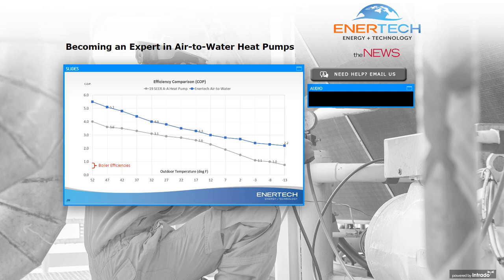If it's a product that's designed specifically for low temperatures and is specifically designed for heating, as you can see from that blue line, even at minus 13 Fahrenheit, we still have a COP of 2.2. And I've always looked at heat pumps, from a design standpoint, as: where do we want to turn it off? If our COP is around 1, it doesn't really make a lot of sense to run that heat pump. But if we can stay in the 2 range or so, then we're better off making heat with the heat pump. I shouldn't say making heat, we're transferring heat, than we are switching over to electric heat.